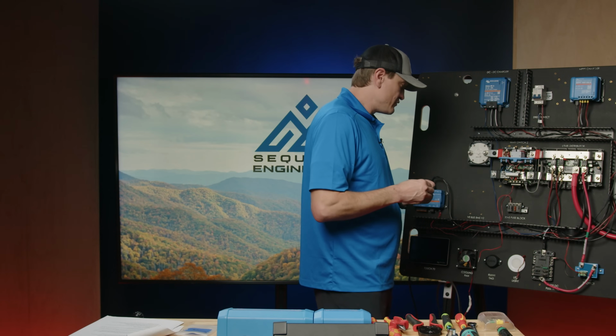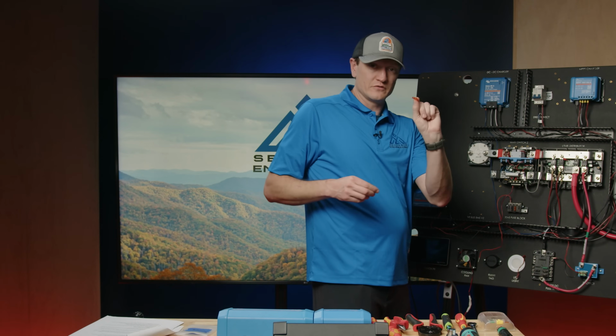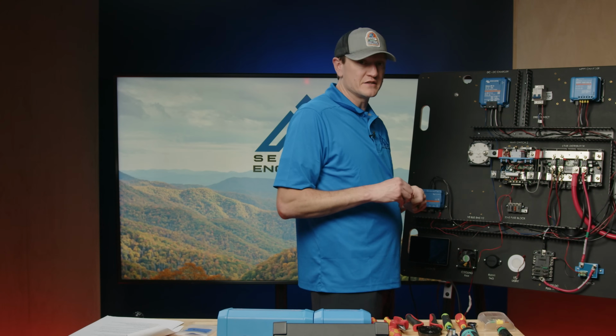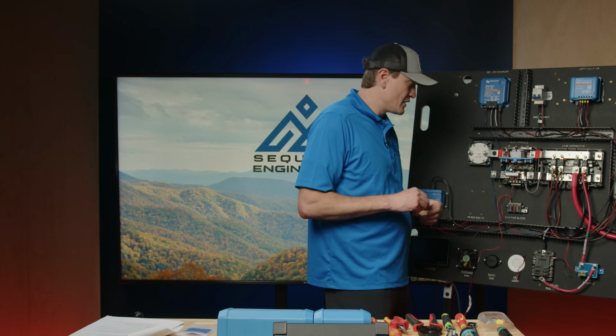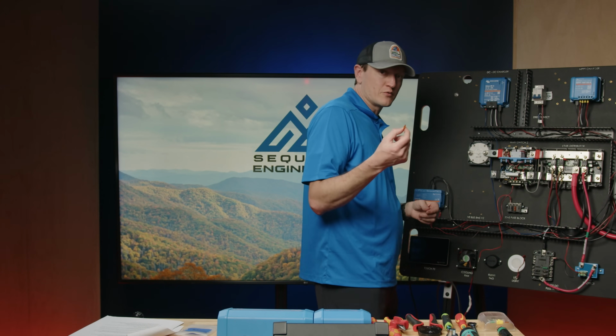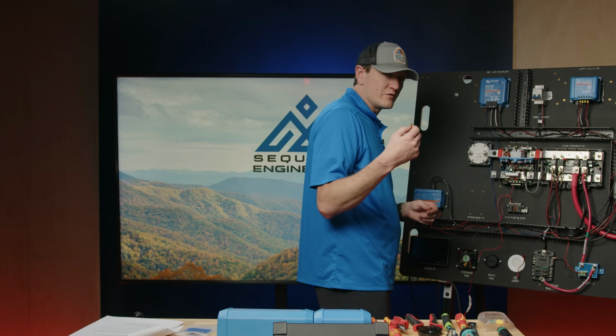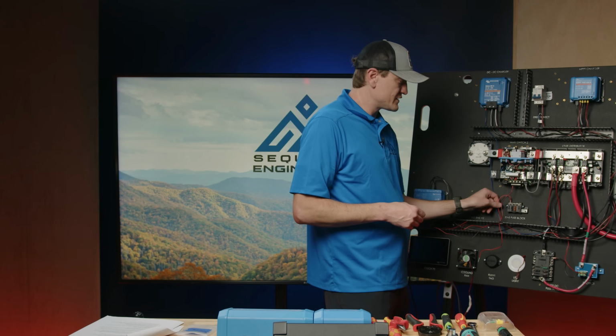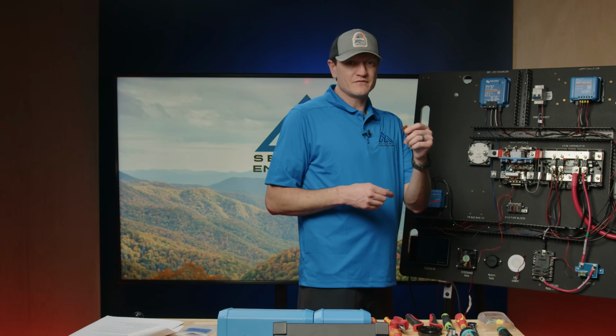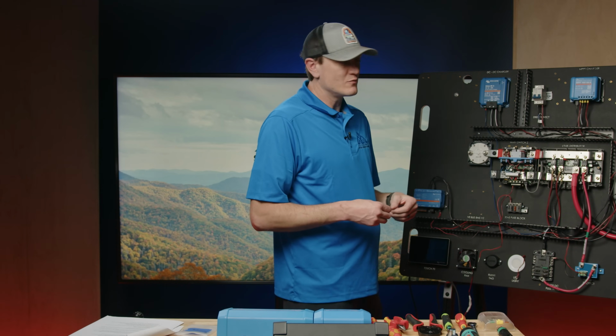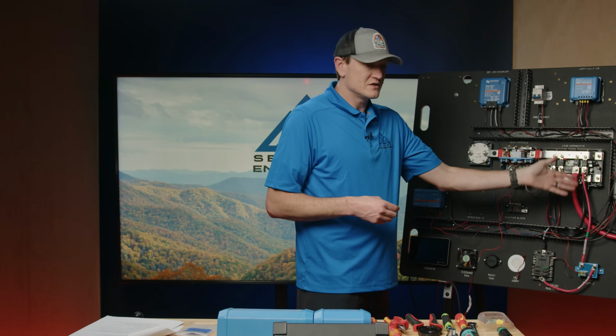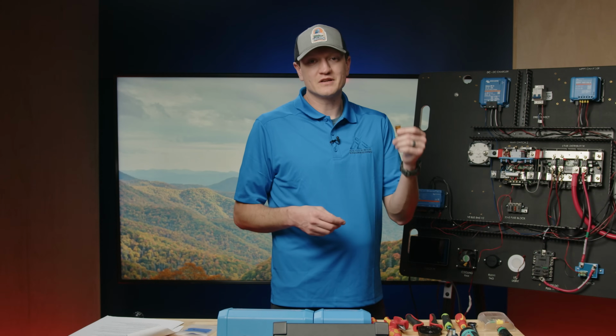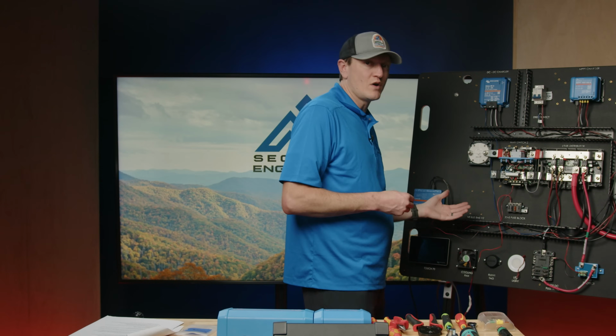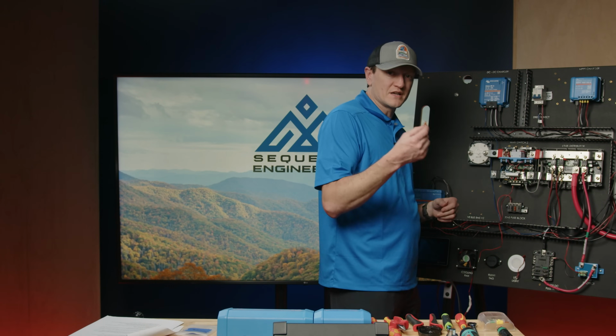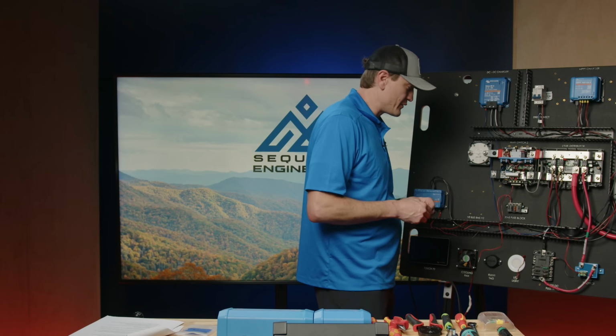This particular fuse is actually a 5 amp fuse, which is oversized for this wire. We'd typically run something in the neighborhood of 1 to 1.5 amps for a wire this size, but you size the fuse and wire the same way you would for any other connection, just for this specific application.